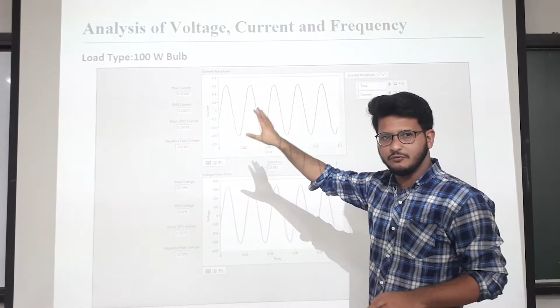As we can see, we are seeing the peak current, RMS current, mean DC current, negative peak current, and its waveform as well. We are also showing the frequency, as this is all for the current waveform and current measurements. Now this graph is for the voltage waveform and the peak voltage, RMS voltage, mean DC voltage, and negative peak voltage. For this purpose, we are also comparing it with the traditional power quality analyzer. Our serial-based power quality analyzer has many functions which the traditional power quality analyzer does not give. With all these multi functionalities, we can compare it with the traditional power quality analyzer, which is the Fluke 43B. As we can see, in the single screen it is only showing the voltage, the frequency, and the current.